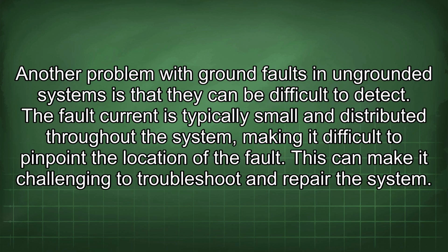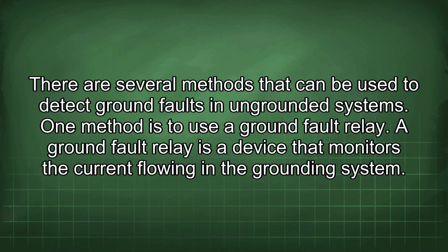Another problem with ground faults in ungrounded systems is that they can be difficult to detect. The fault current is typically small and distributed throughout the system, making it difficult to pinpoint the location of the fault. This can make it challenging to troubleshoot and repair the system. There are several methods that can be used to detect ground faults in ungrounded systems.